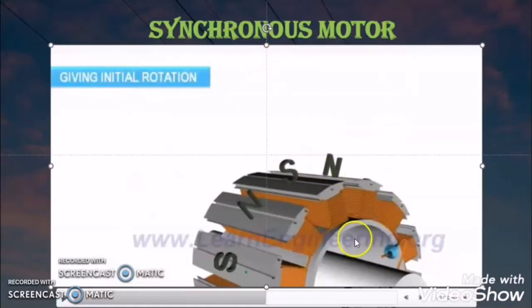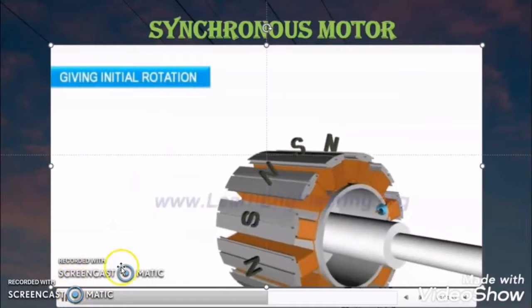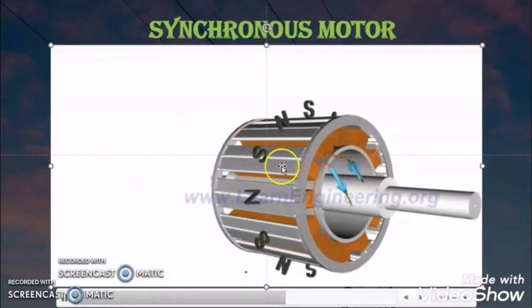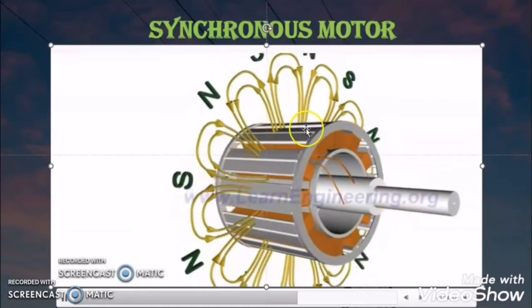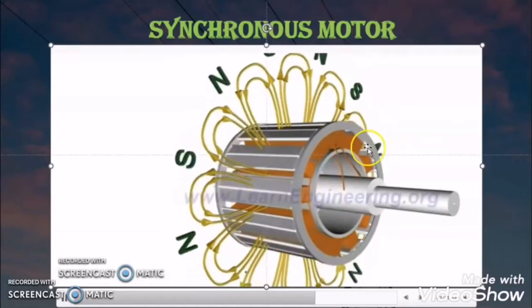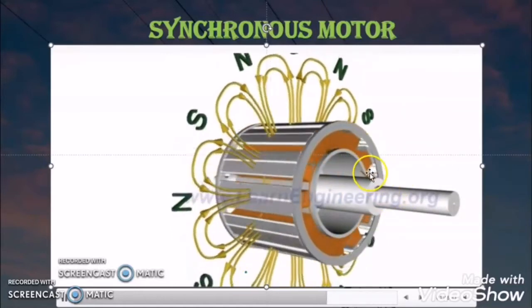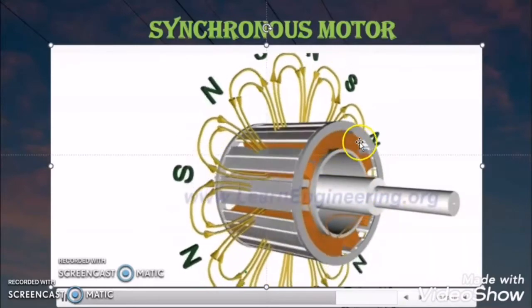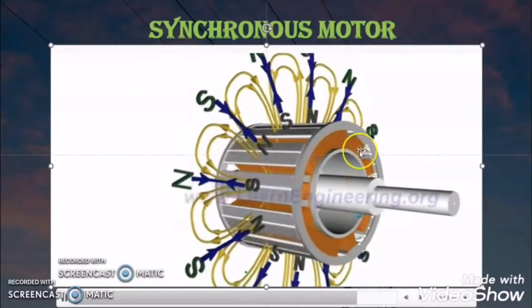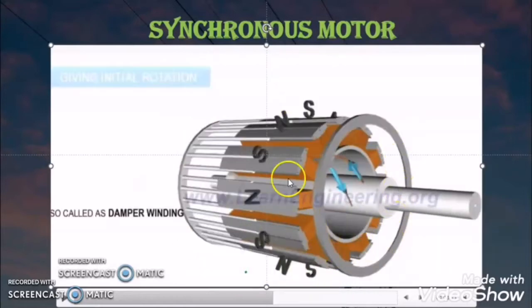It results that the synchronous motor rotor will not start rotating at the time of starting. In order to overcome this problem, we add end rings connected with bars so that the synchronous motor will start as an induction motor. Once the synchronous motor reaches its rated speed by starting in this method, then we energize the DC power supply to the rotor winding. This end rings and bar arrangement connected in the synchronous motor is called damper winding.